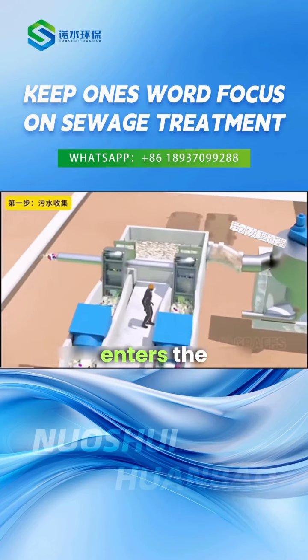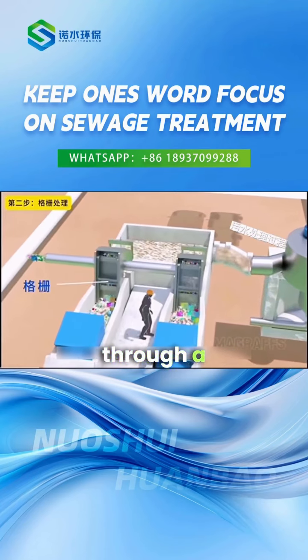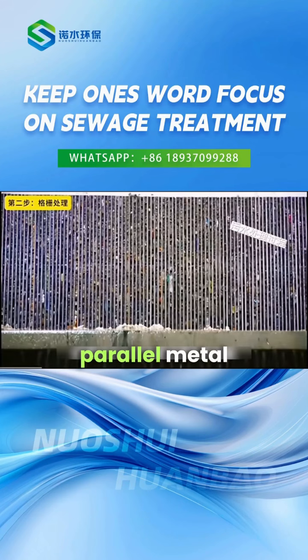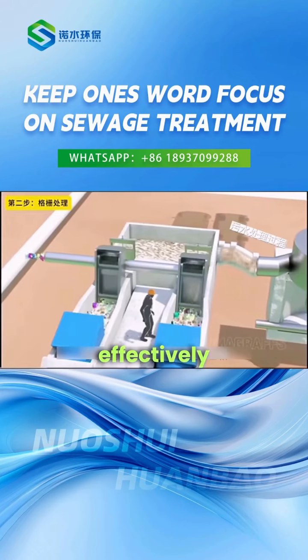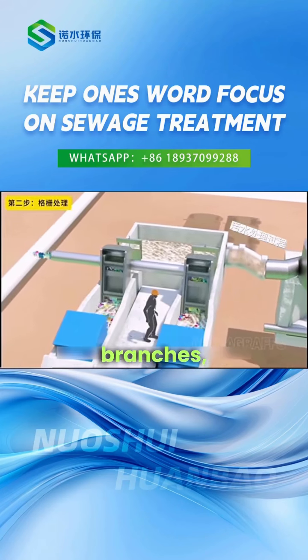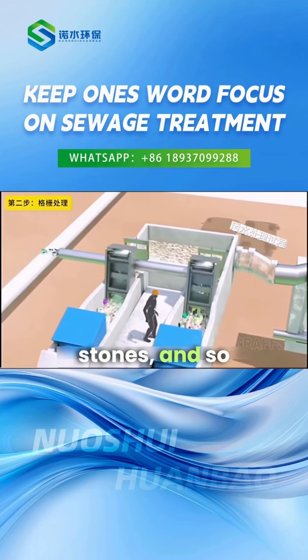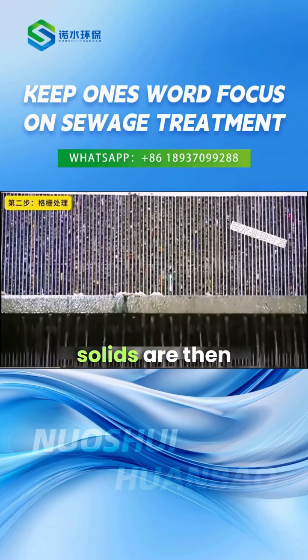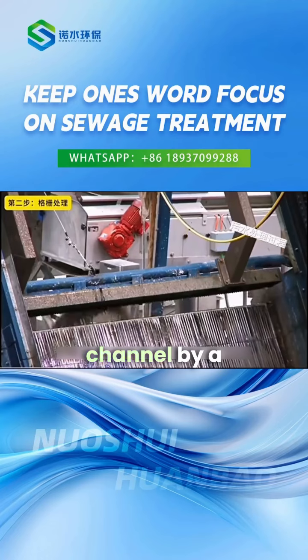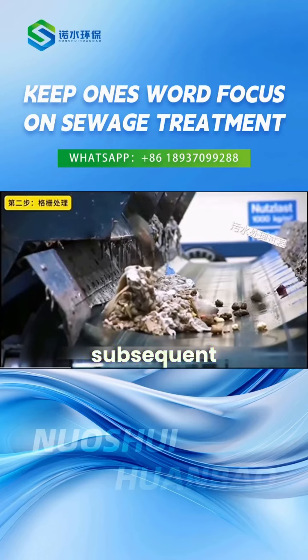Once the wastewater enters the treatment plant, it first passes through a screen. The screen is made up of parallel metal or plastic bars, which can effectively intercept larger solid debris such as branches, plastic bags, stones, and so on.